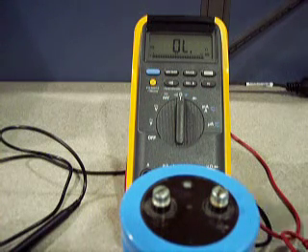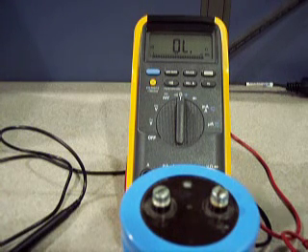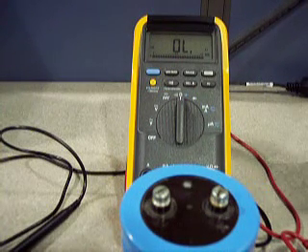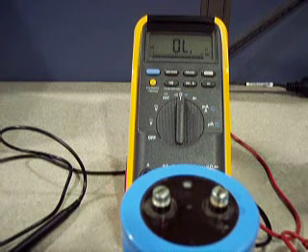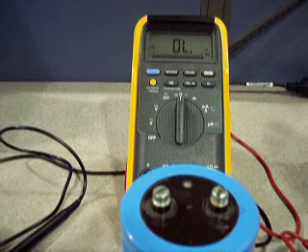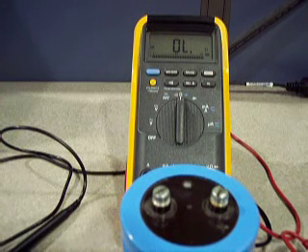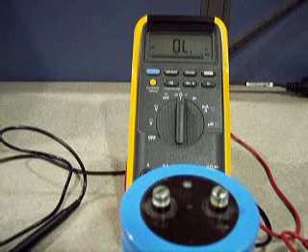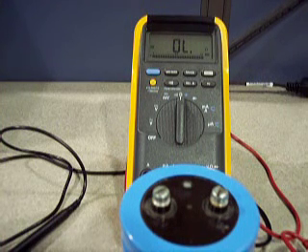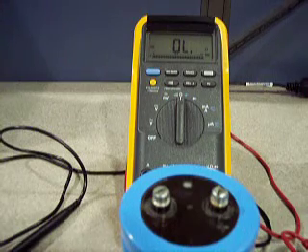And if we were doing quick measurements in a circuit and we're using continuity and there happens to be some voltage stored on a capacitor between a couple wires or some other source that has managed to be stored in some other means, or there's a bleed off in the circuit, when we take these measurements with the meter, it is possible that we could measure continuity between 2 points that there really is not a continuous path. There just happens to be some legacy voltage out there where things have not discharged, or if the circuit's live, again it could indicate that there's continuity between two paths.